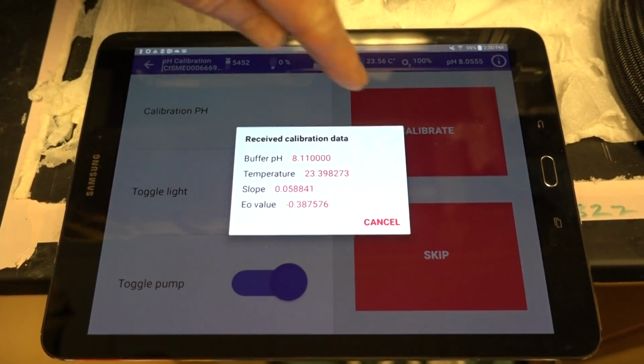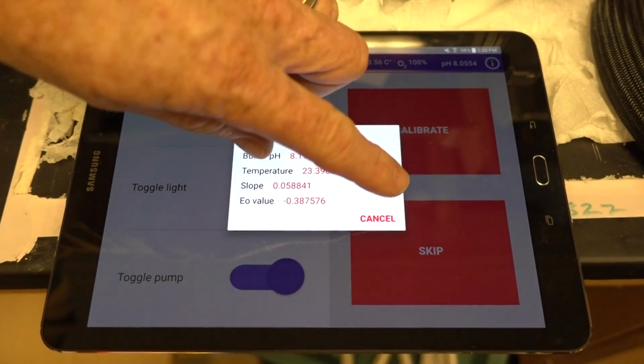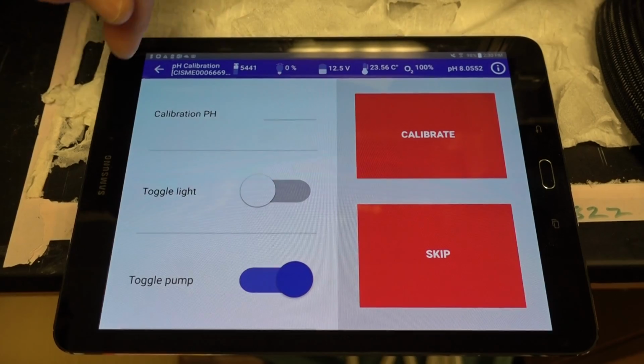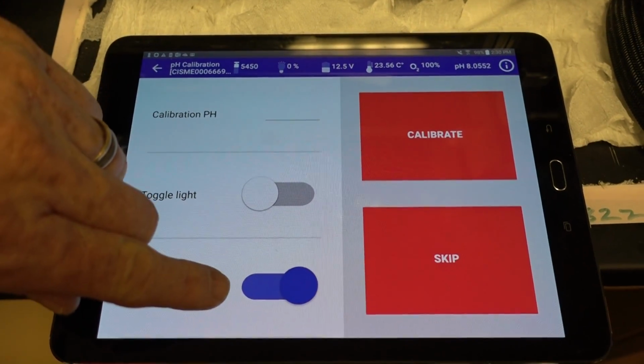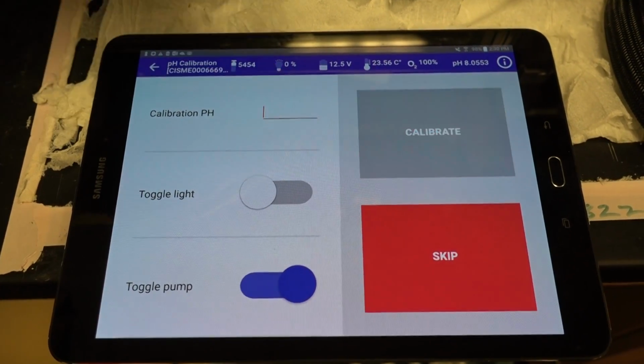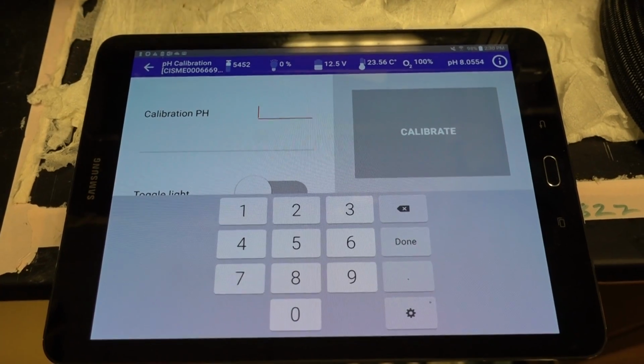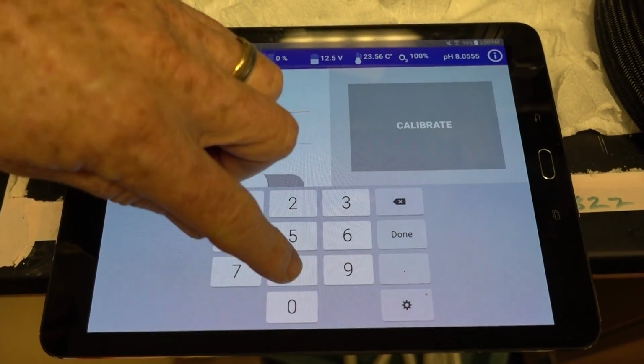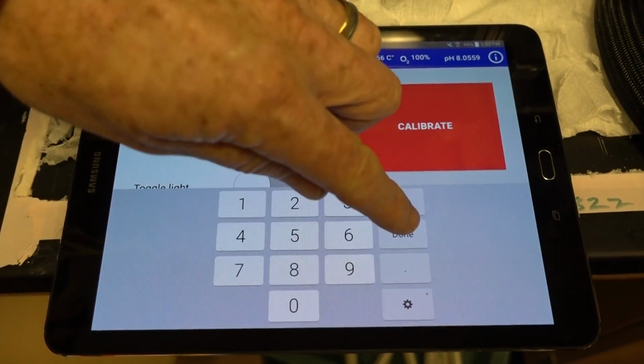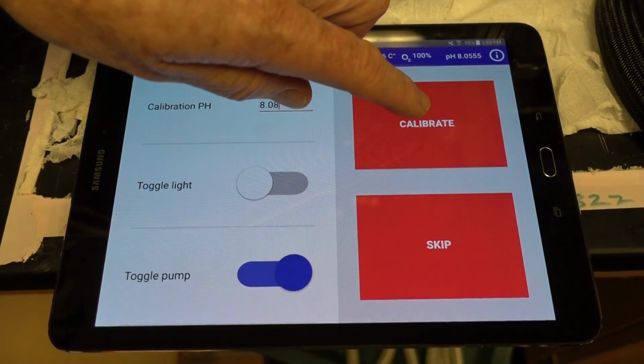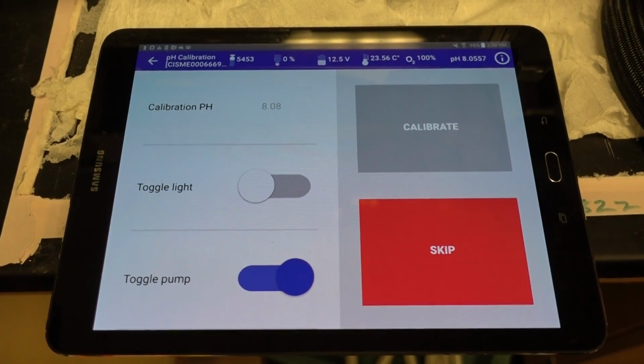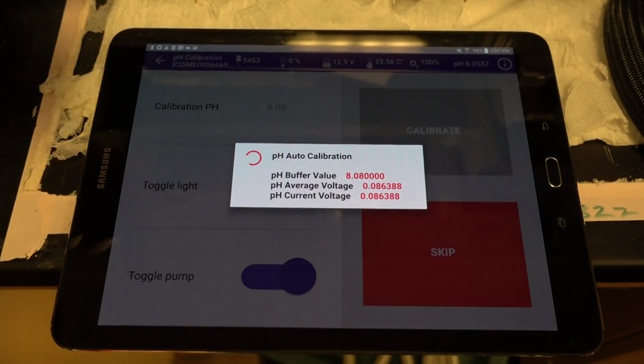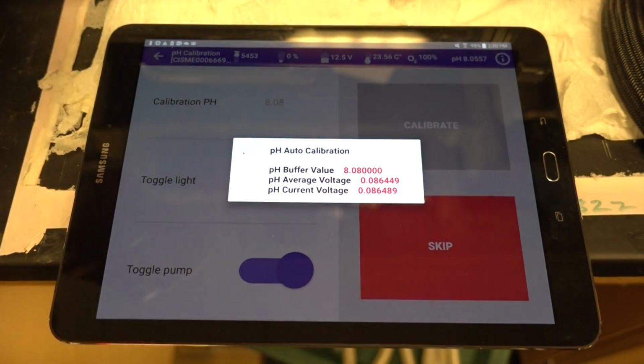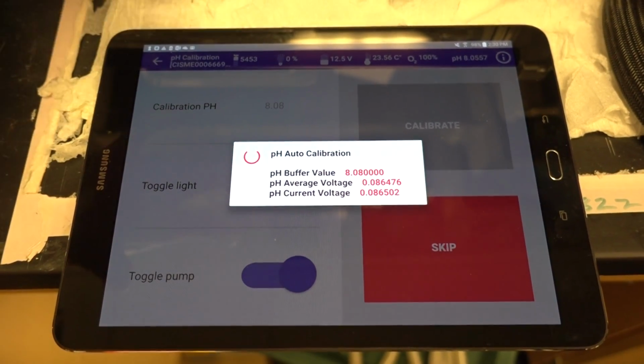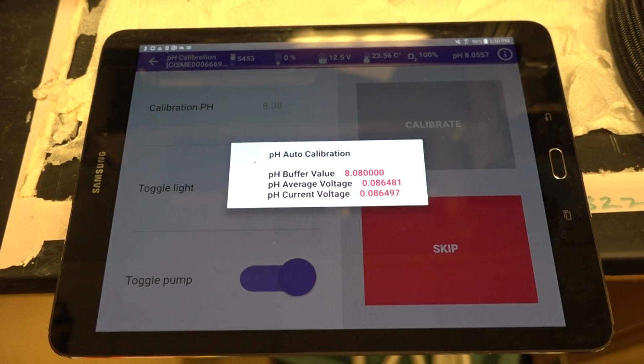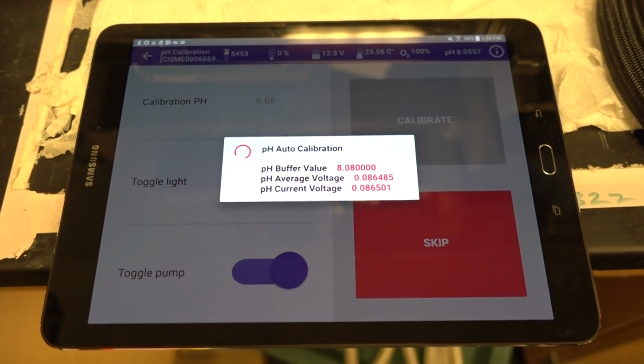Again, it shows us the current factors that are stored in memory. I'll hit cancel. We keep the pump toggled on. We'll enter the pH, the known pH from our buffer. 8.08. Done. And I'll hit calibrate. Again, it will cycle through 100 measurements of the raw voltage and plug that into the equation in order to be able to generate the calibration factor for this electrode.